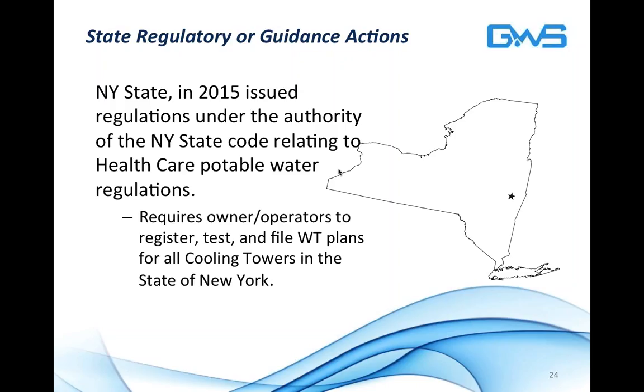It became an expansion into the cooling tower sector, not necessarily the potable water sector in these buildings. For cooling towers, it now requires owners and operators to register their cooling towers, do periodic Legionella testing, and file their water treatment plans with the state for any cooling tower that exists within the state. It's really a quite sweeping set of new regulations, so these are must-pay-attention-to because they are regulations in New York State.